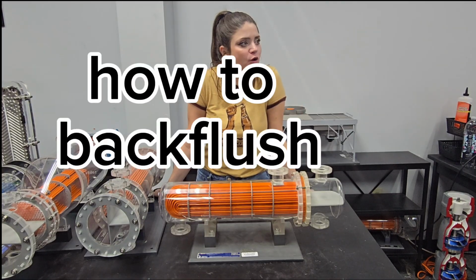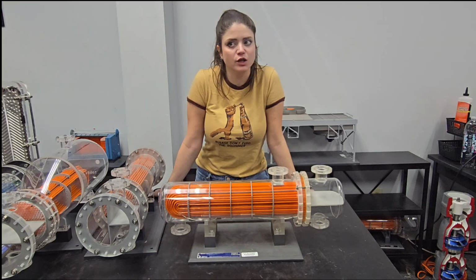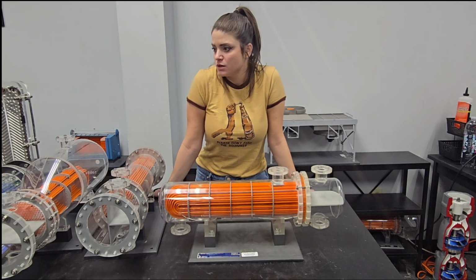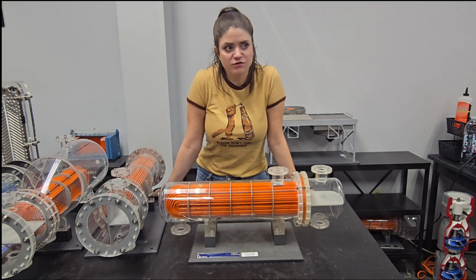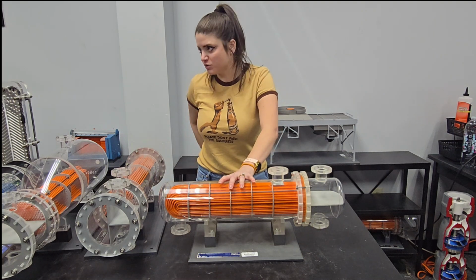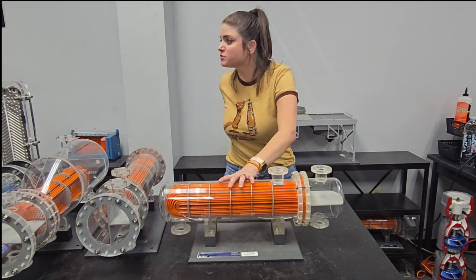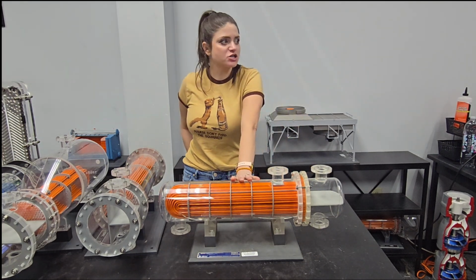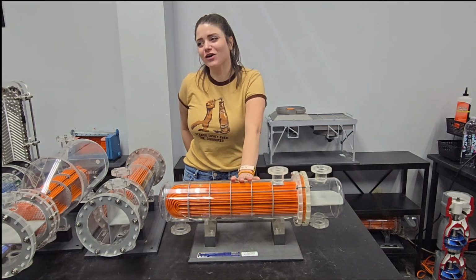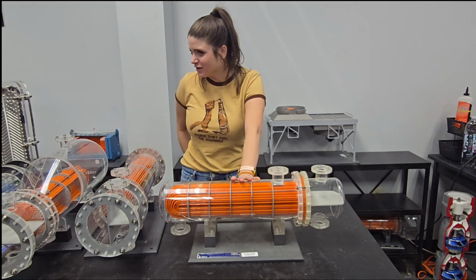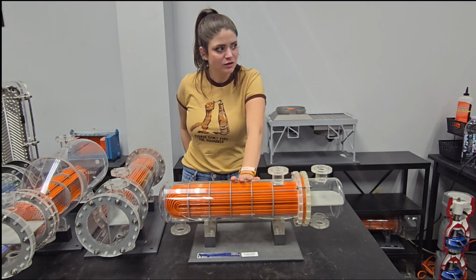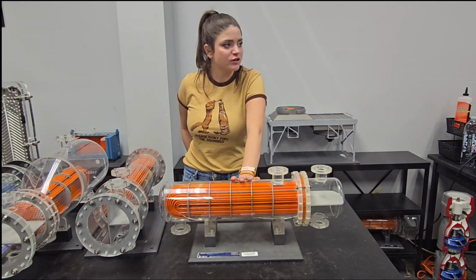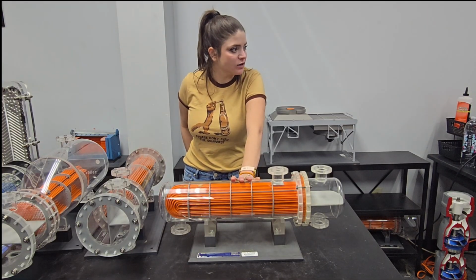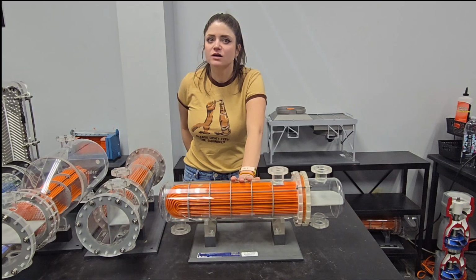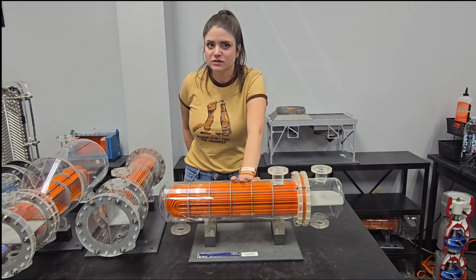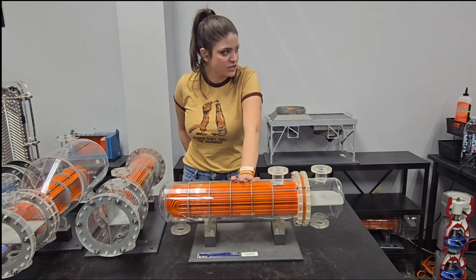Backflush. So what are we gonna do? What are we gonna close? The isolation point for the suction inlet of the tube side. If our cooling water's on our tube side, we're gonna close the inlet on our tube. Yep, correct. And then what are we gonna open? The butterfly valve, or the drain valve, the drain line on the inlet, downstream of the isolation point.